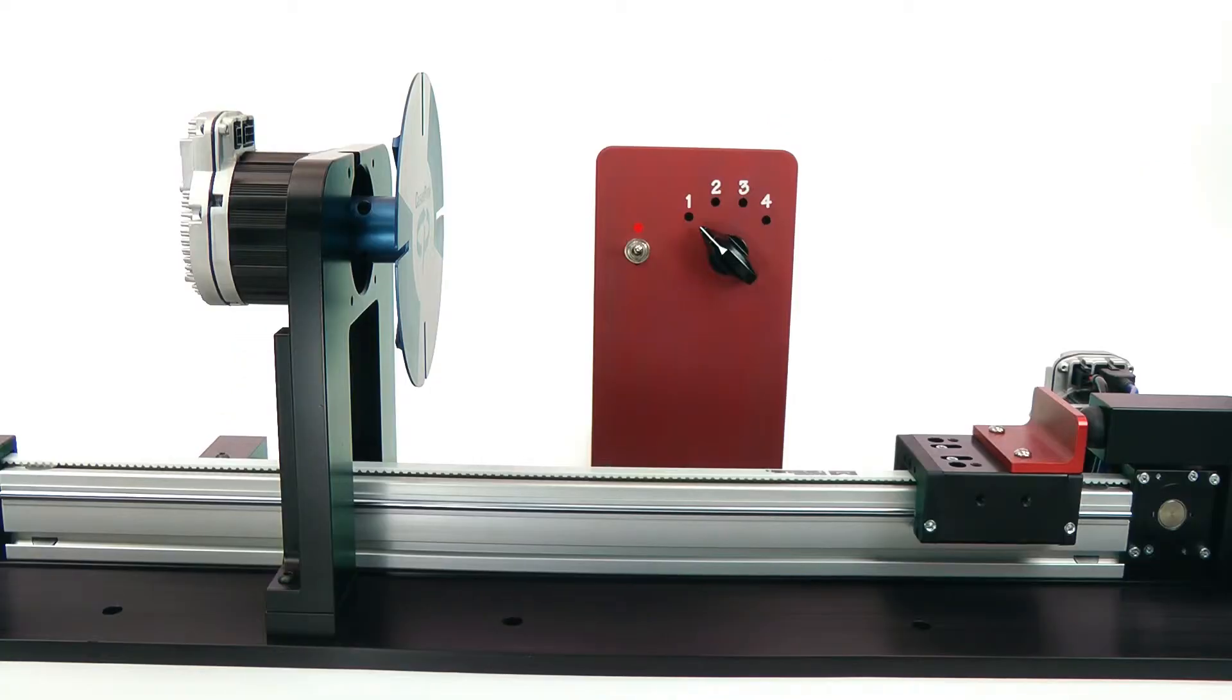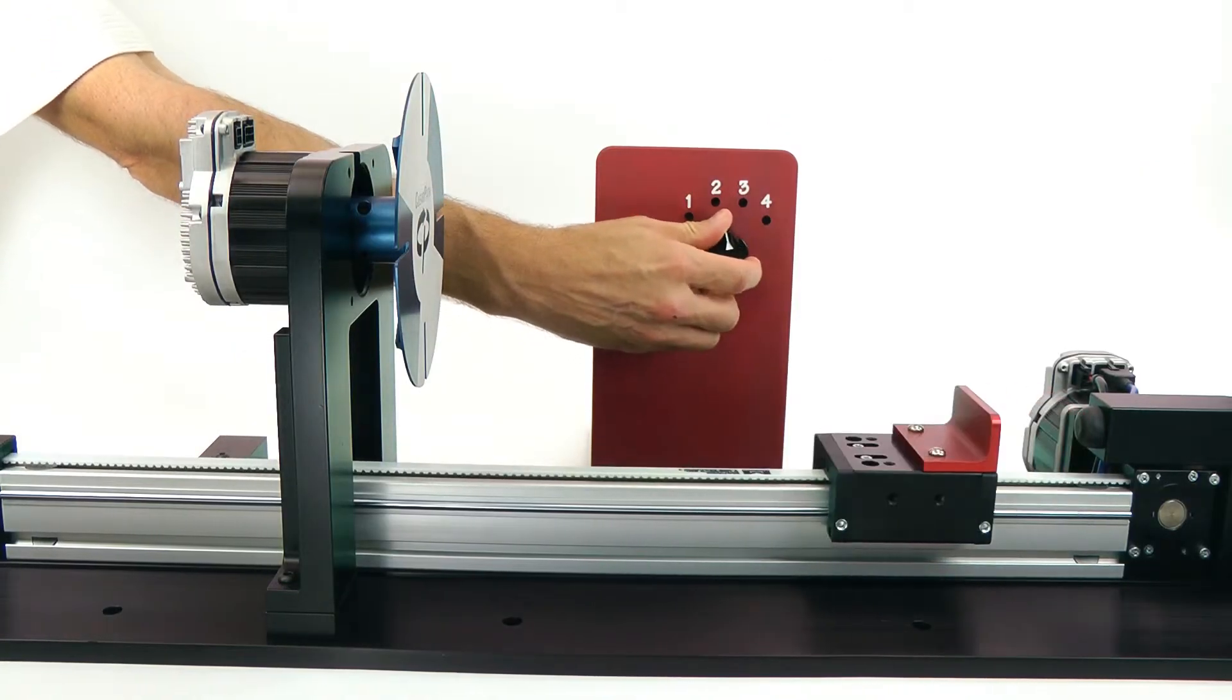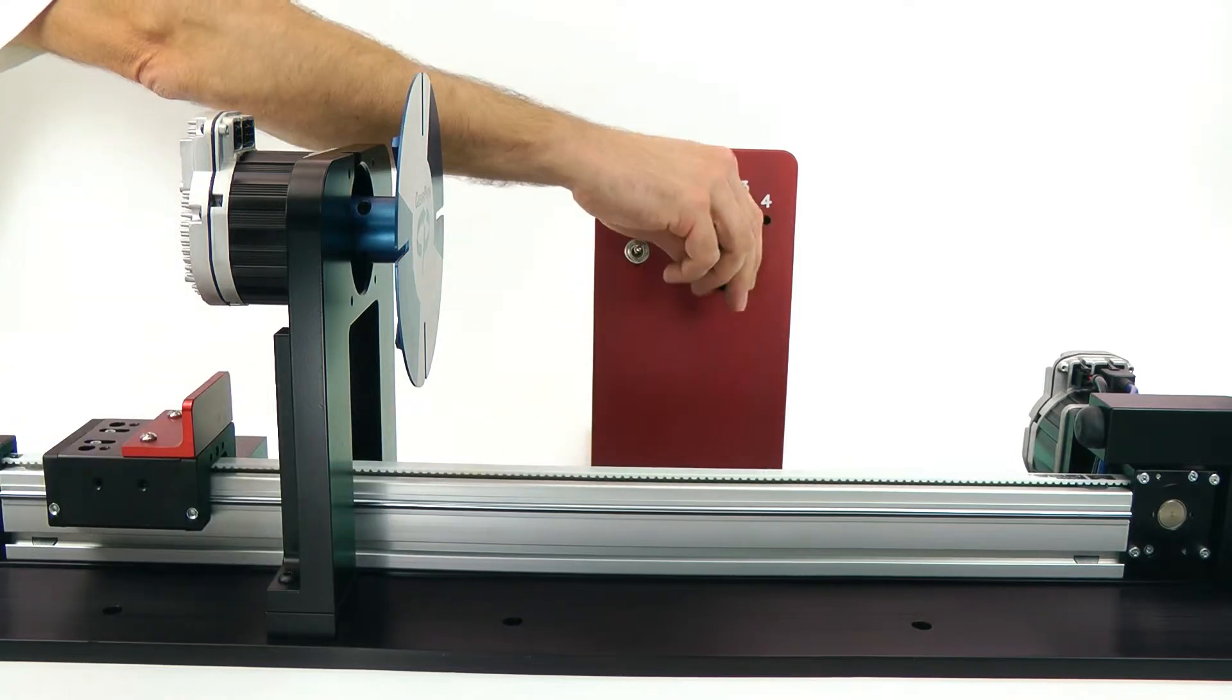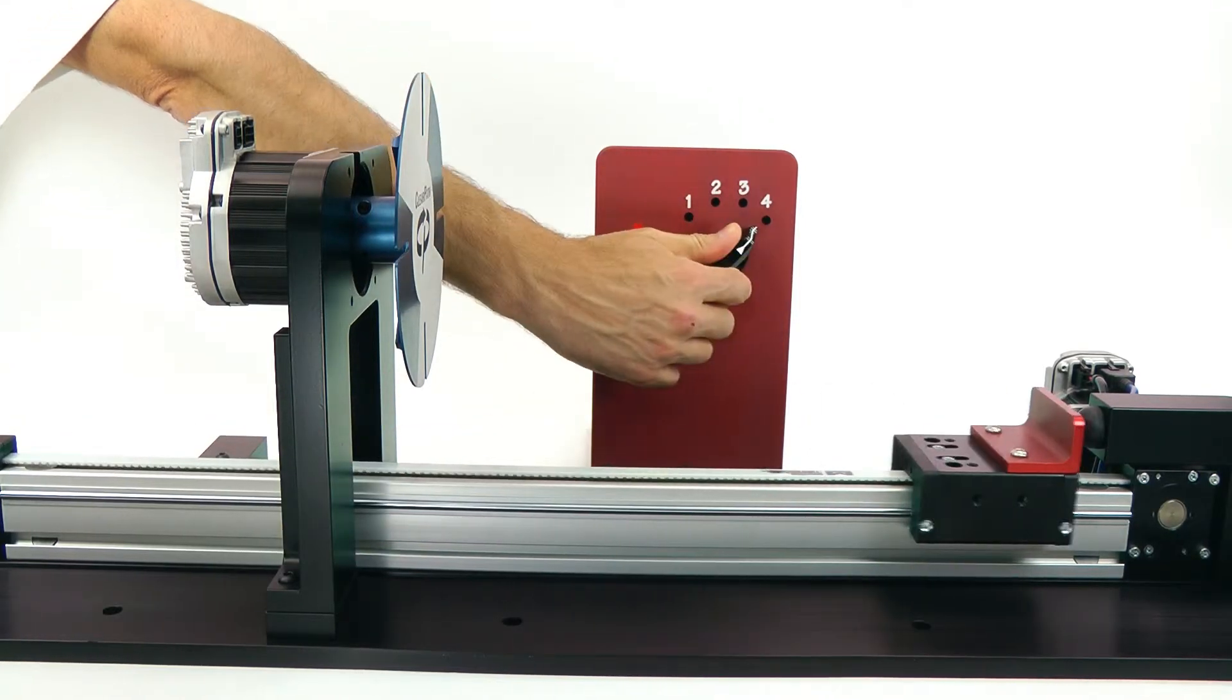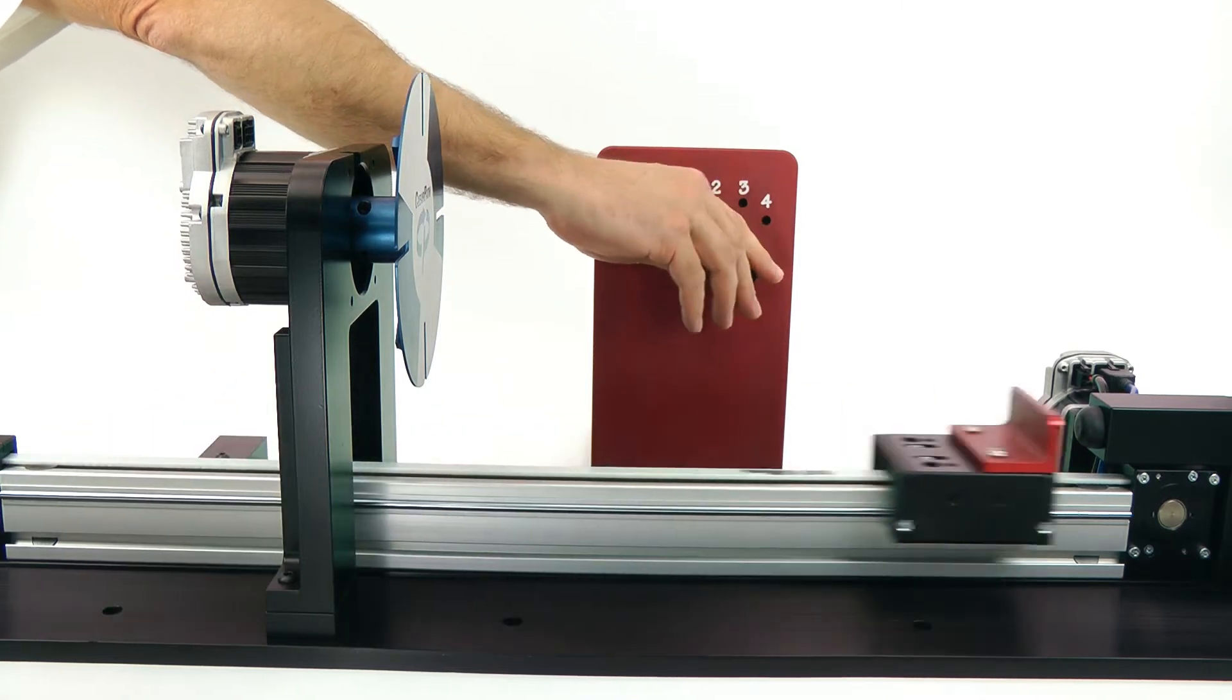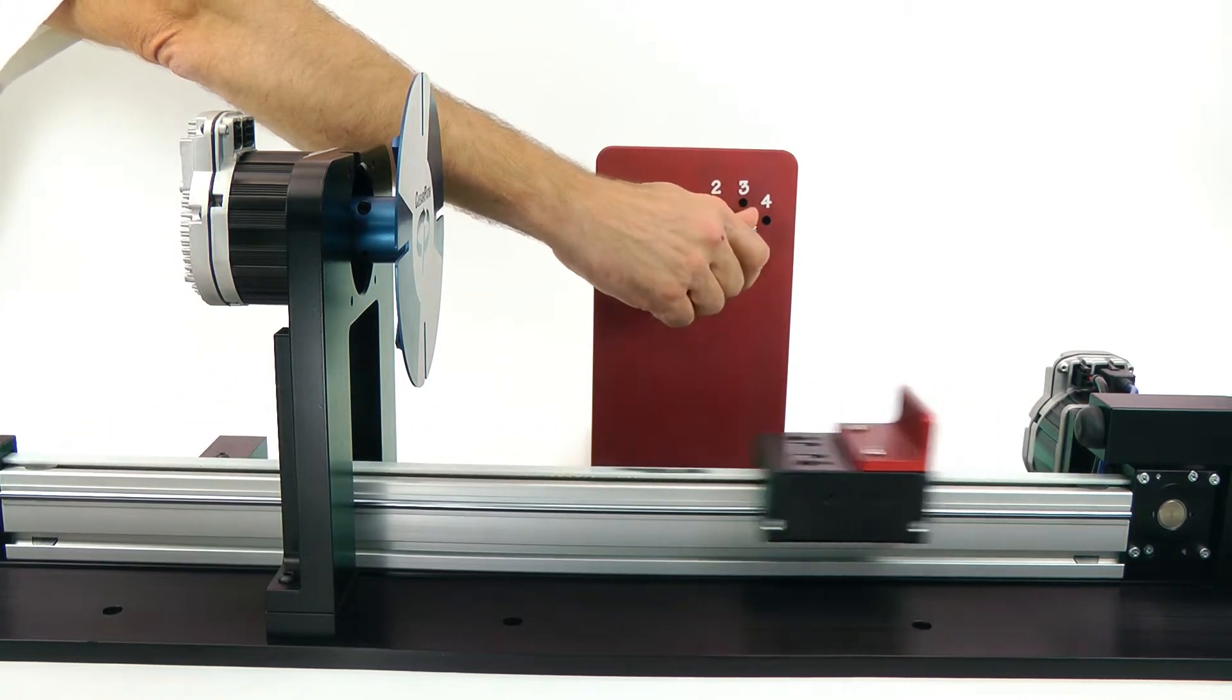Now, moving between the four absolute positions is as simple as selecting the desired combination of A and B inputs. I'm doing that with a rotary switch, but of course you could also do this with many other digital signals, like digital outputs from your PLC.